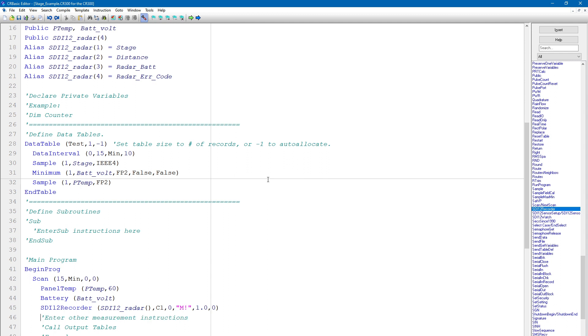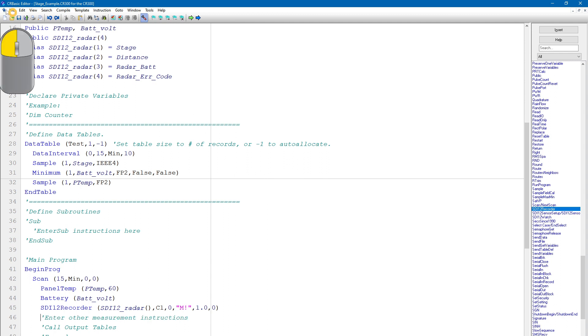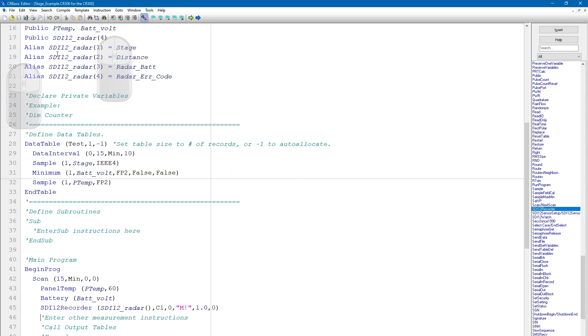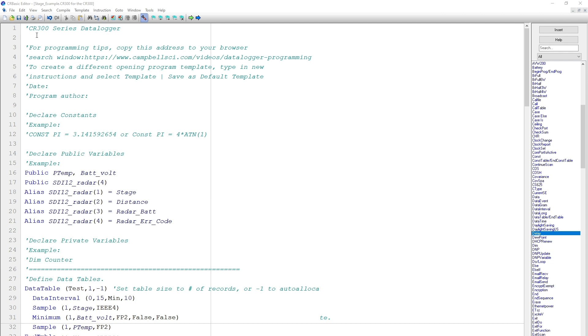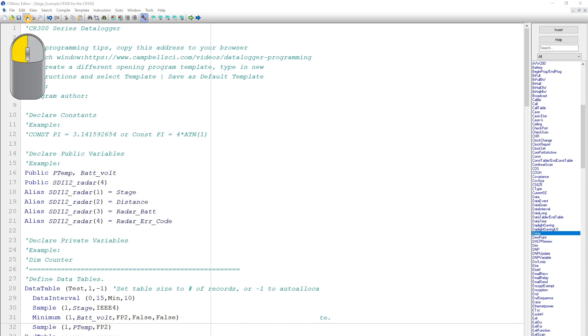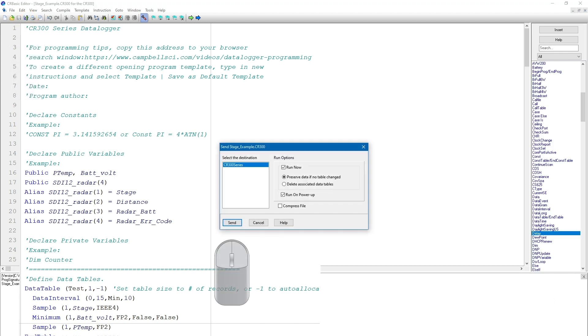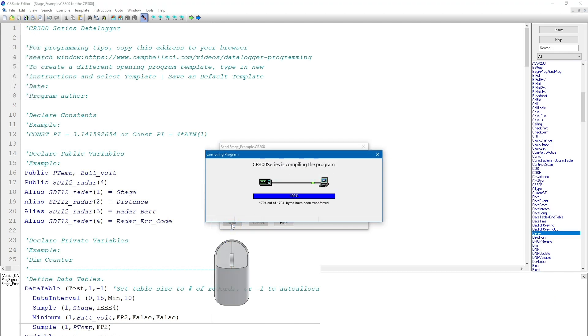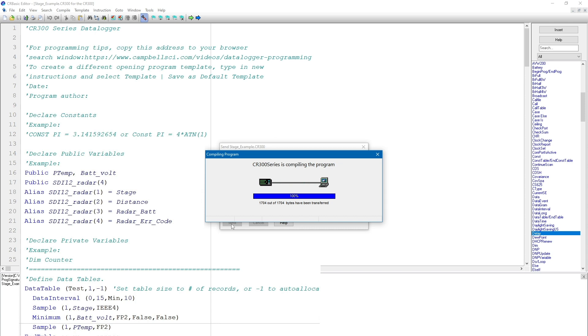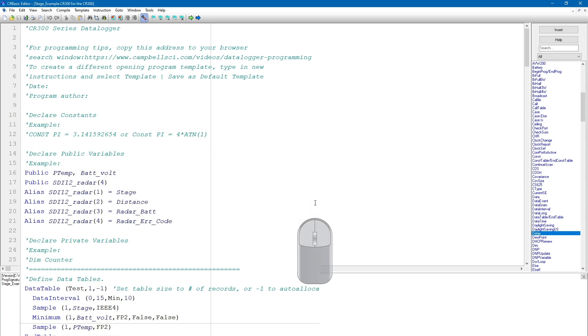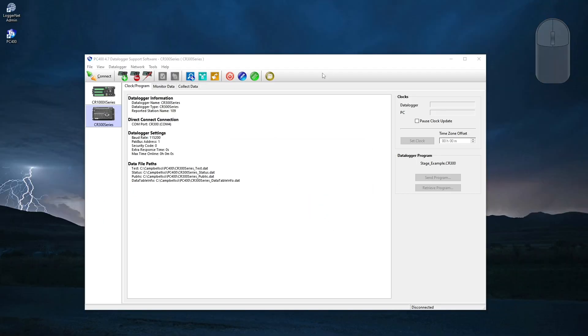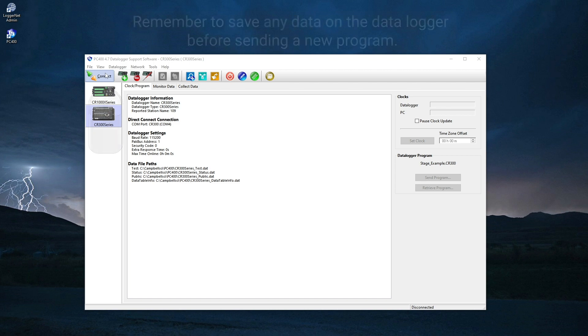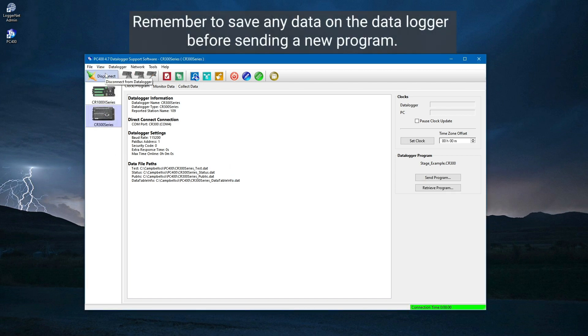I will save the program and make sure it compiles. It compiles OK, which means I can load this program into the data logger and get 15-minute stage readings. Now I will send the program to the data logger using the Compile, Save, and Send button in the top left corner. I like to use this button in the CRBasic Editor because it's convenient to send a program directly from the CRBasic Editor, but this should be used with care because if I have unsaved data on the data logger, the data will be erased. If there is any unsaved data on the data logger, make sure to save it before sending a new program to the data logger.